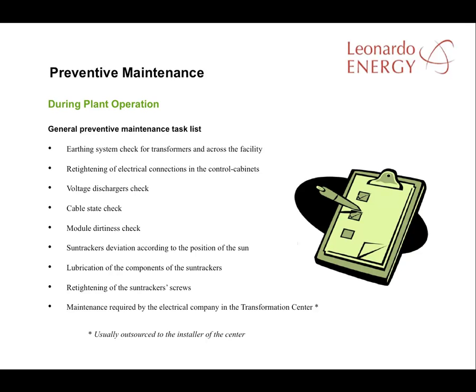In this slide, we can find a list of features that generally require preventive maintenance: a check on the earthing systems; tightening of electrical connections in control boxes or control rooms; a check of voltage dischargers and the state of cables; checking the dirtiness of modules and checks for the appearance of hot spots on those modules; verification that required maintenance by the electrical companies in the transformer centre has been completed; and if there are sun trackers, a check on their deviation from the optimal position in relation to the sun, and records of tightening and lubrication of moving components.